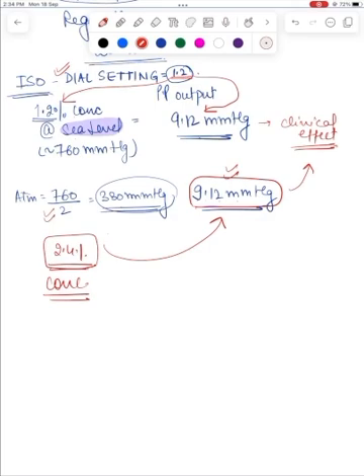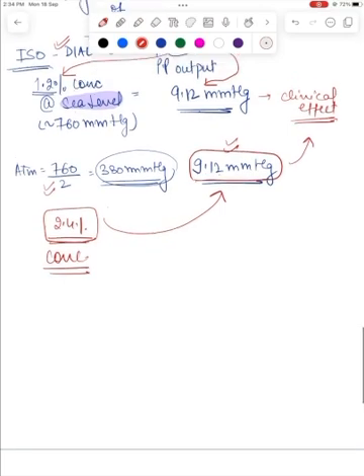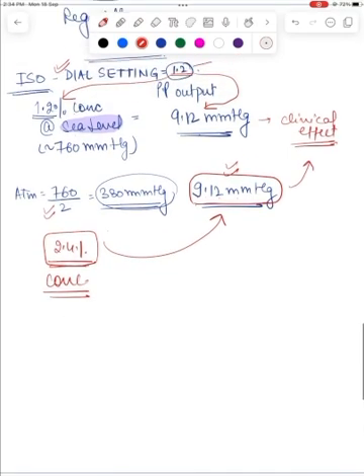Therefore, when using a variable bypass vaporizer there is no need to adjust the dial setting. A dial set at 1.2% will deliver the same partial pressure regardless of altitude, even if the inspired concentrations of the volatile agent may change.